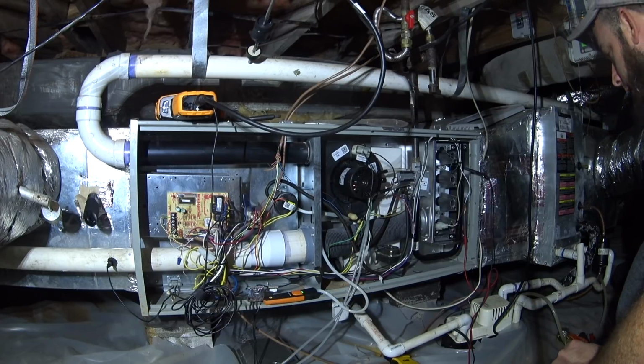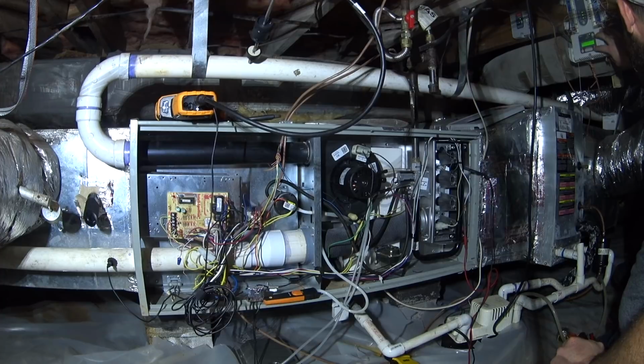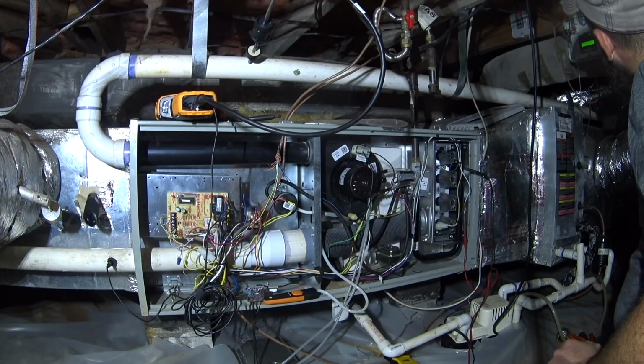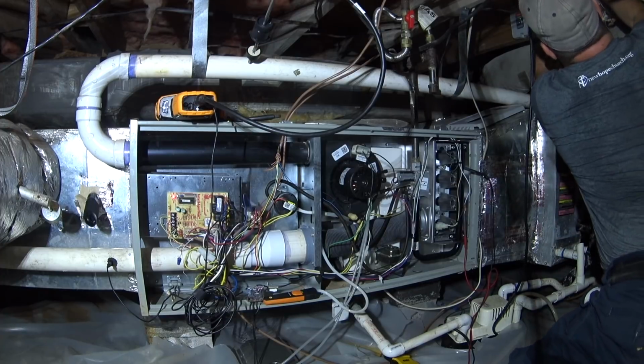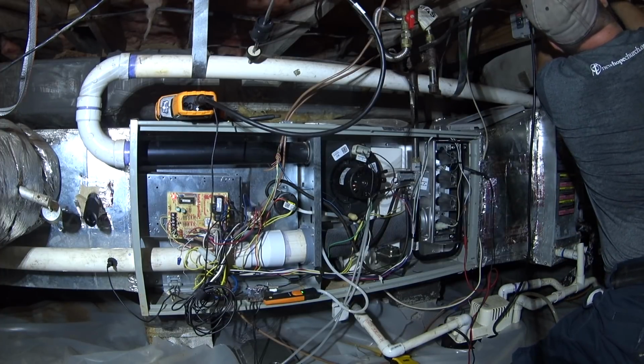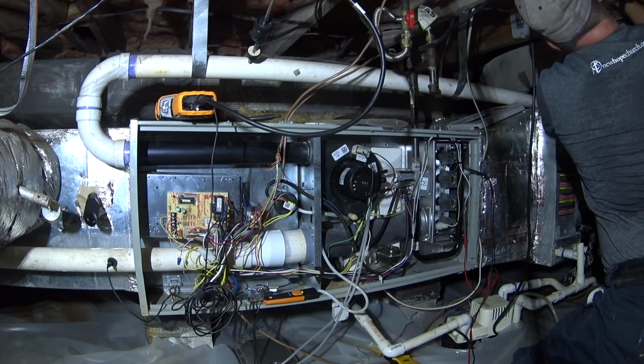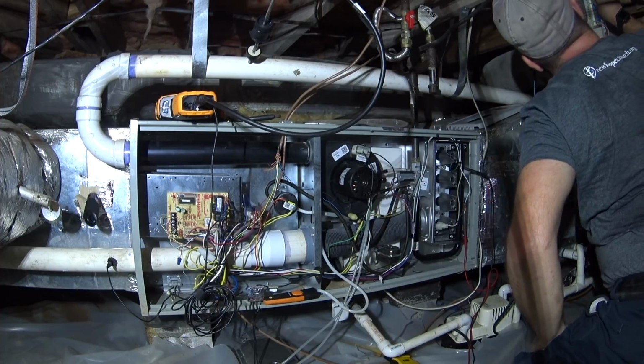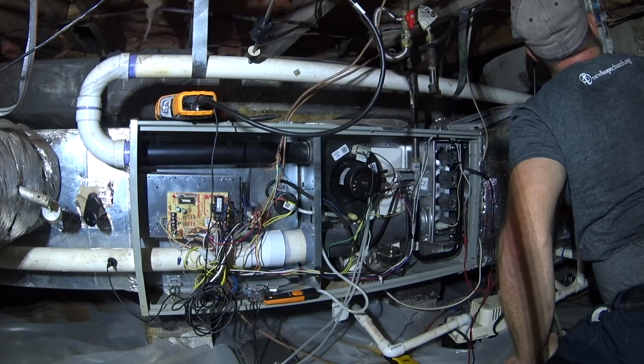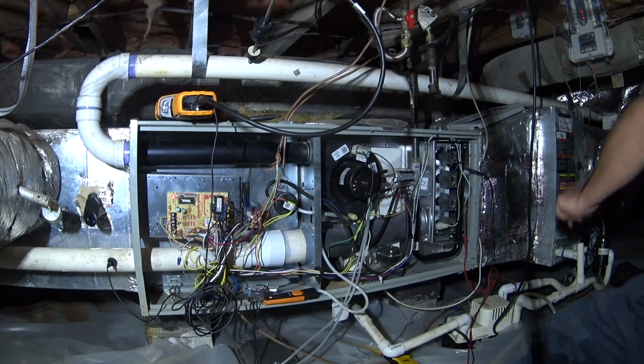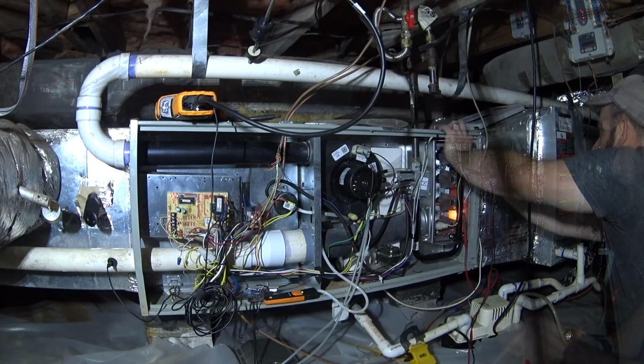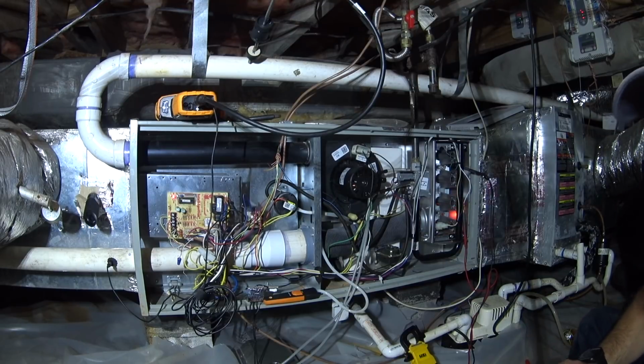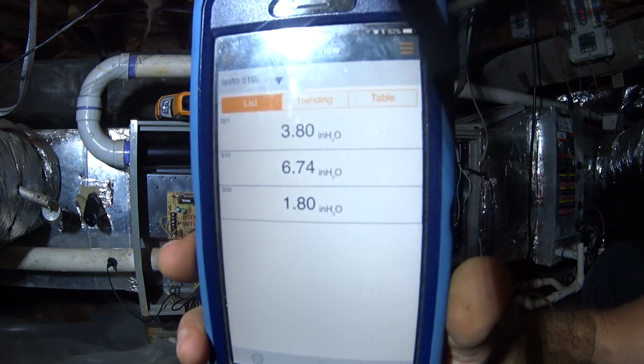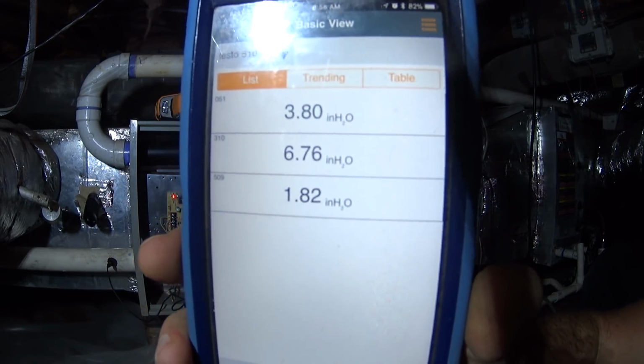Alright, power is back on. Override purge. And I'm going to disconnect the zone damper common on all the zone dampers so that I can just run the thermostats from the zone board by jumping out one thermostat. Alright. We'll get flame sensor. Alright. So inlet is 6.7, outlet is 3.8, and the manometer is running a negative 1.8.